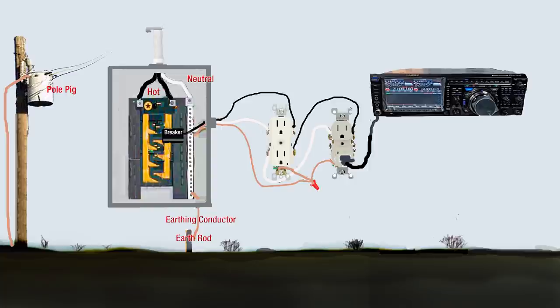For most of us, our power comes from a transformer located on a pole. That transformer is called a pole pig. It transforms the high voltage, either somewhere in the neighborhood of 4,000 to 6,000 volts typically, down to 240 volts. It's three wires, neutral, 120 on each side, go to the weather head, and then down into the main electrical panel. That panel is grounded with some kind of rod or water pipe or ufer ground.